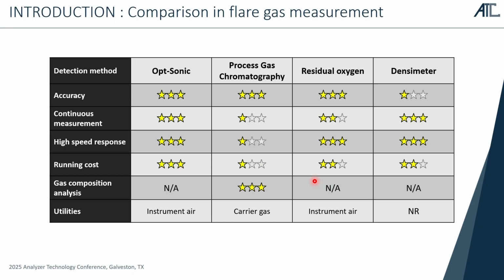Accuracy is quite high, but it's not a continuous measurement. And then our response is not very fast. And then running costs, there may be some consumables that need to be replaced, and then calibration is required. But the strong point is gas composition analysis. But carrier gas, like helium, is required for the measurement.